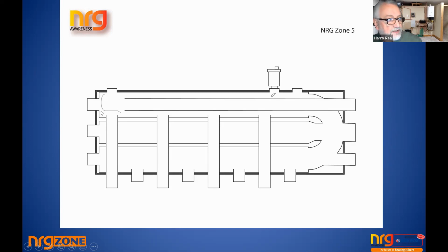There's another very important thing. When water flows in here or here, water will be tending to travel in a straight line. But to release air from water, you need two things. You need to break the water flow up so that the water becomes turbulent. And when it does, because it's the hottest water, the air will break away and rise to the top. And the distance from where the water comes in, whether it comes on this side or this side, is about 5 to 7 times the diameter of the pipe delivering across here. So in that distance, all of the air travels to the top and is scooped away. So people who use NRG Zone regularly would say that the system becomes very quiet very, very quickly.